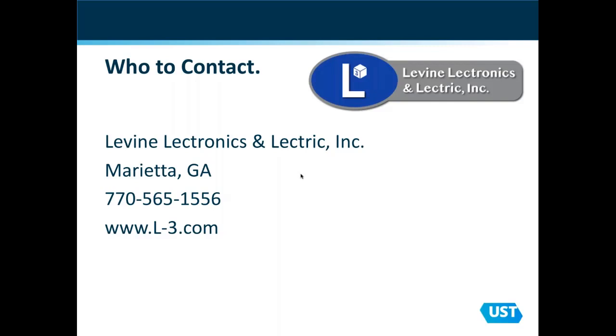The next question that came in is, is the equipment listed by an OSHA approved NRTL? And so I'm going to assume that's a nationally recognized testing laboratory. And perhaps this person is referring to like a UL listing or CSA US? Right, UL listing for some of the smaller sizes up to, I want to say, 250 kVA. And it's for common voltages. And then anything beyond that typically, as you get into the bigger sizes, people want little nits and gnats to make it custom to their application. So that makes it very difficult to UL.